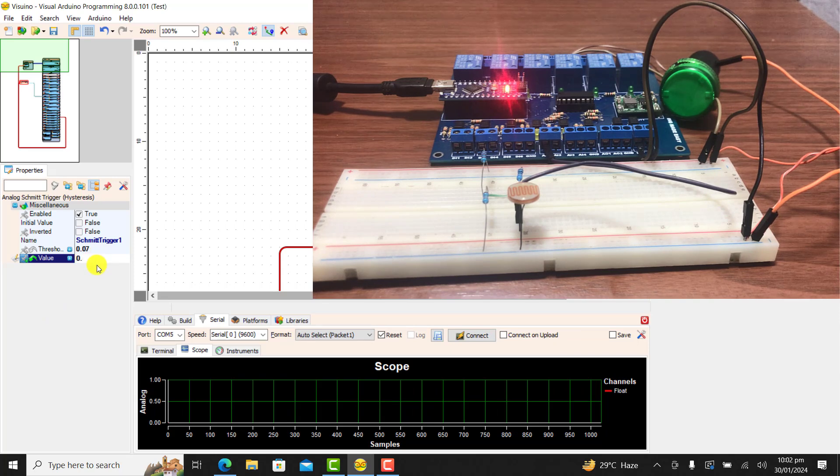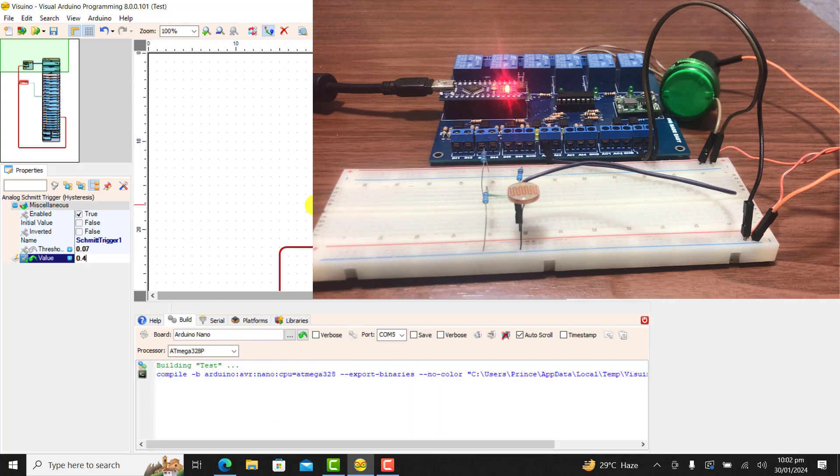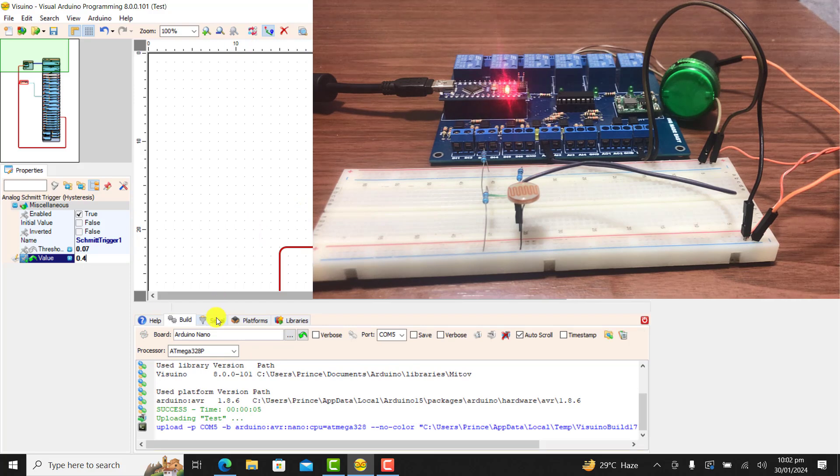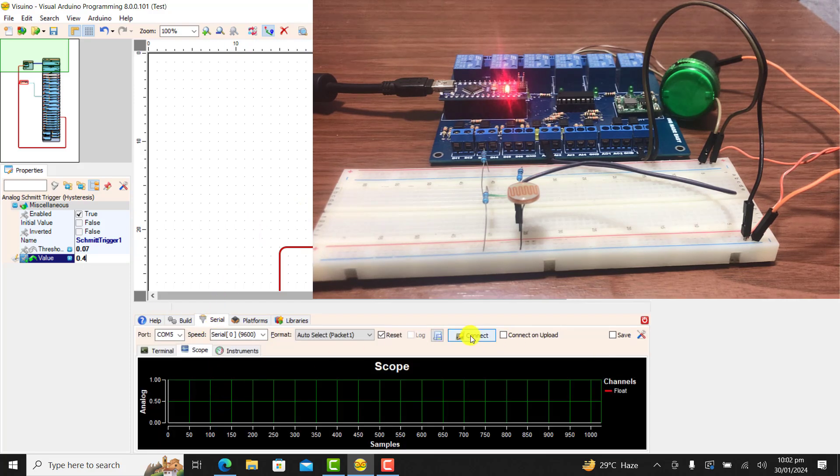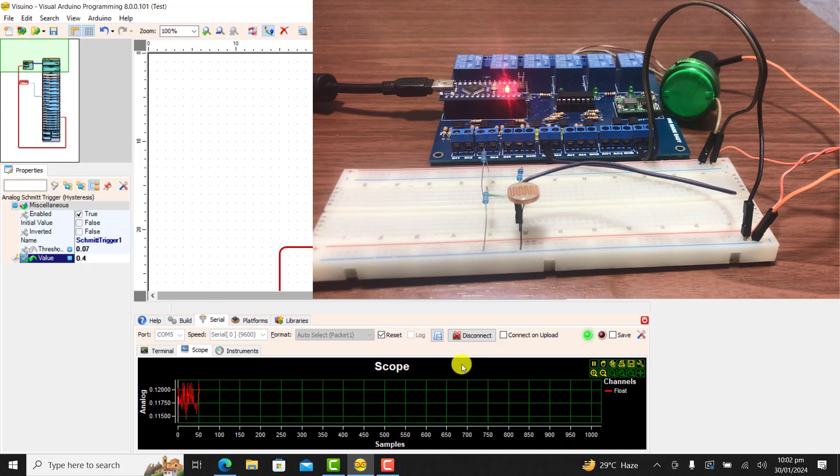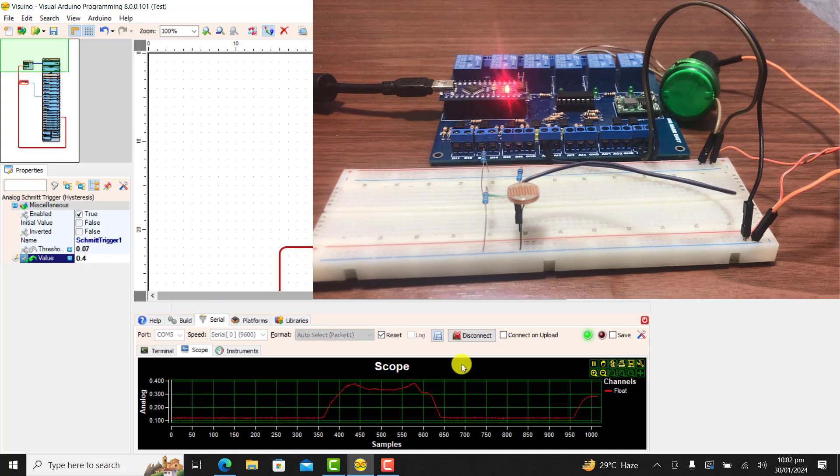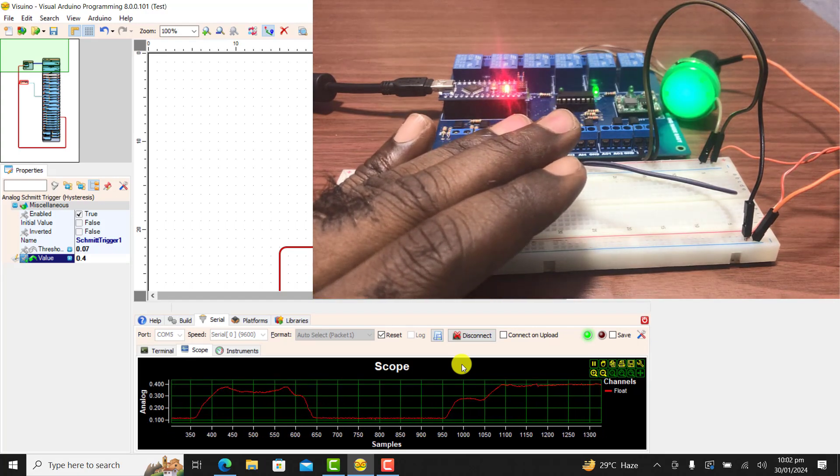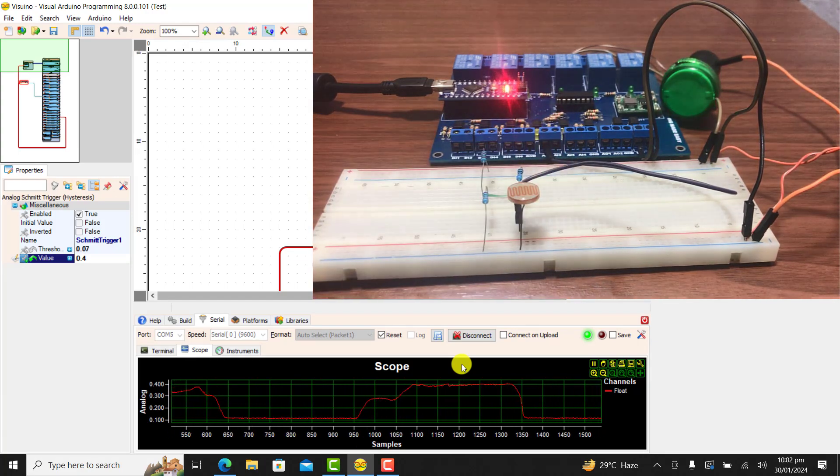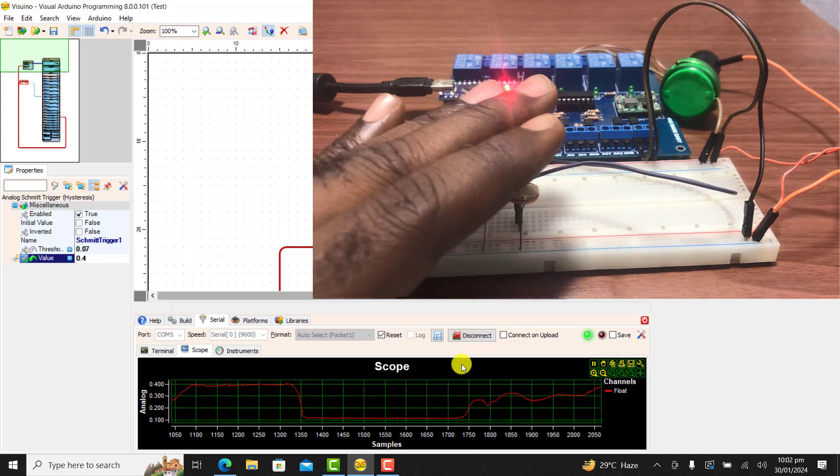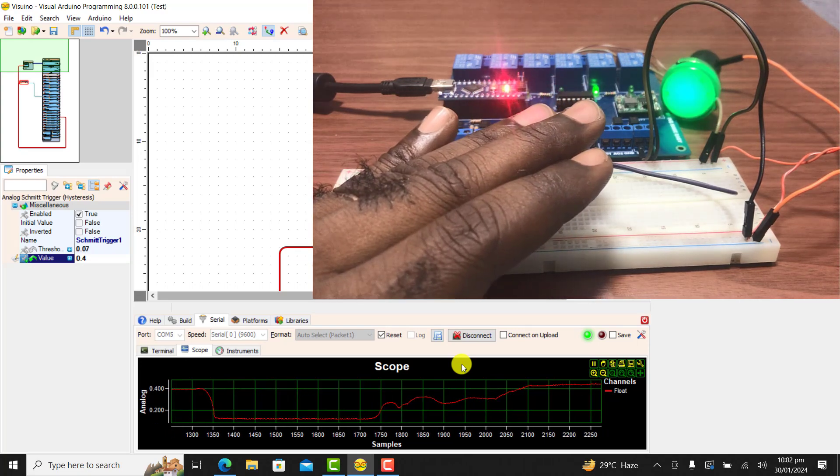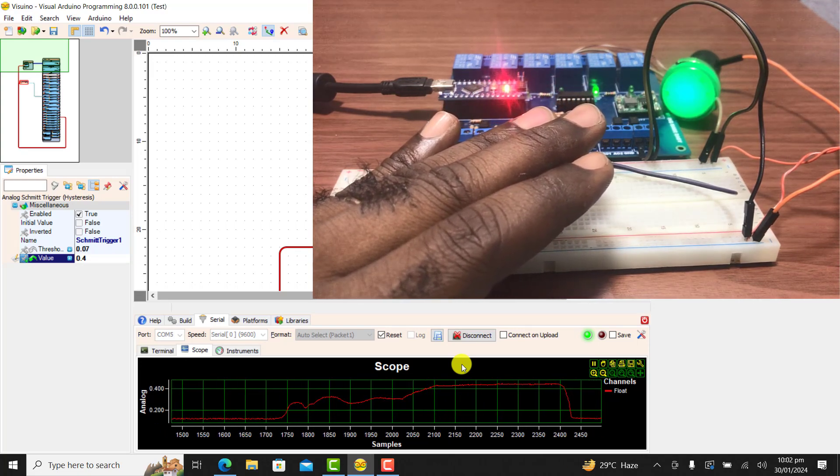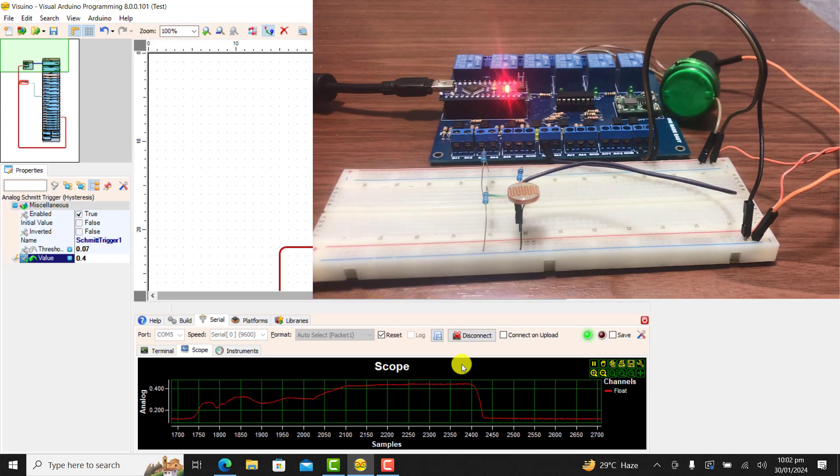I change the value now to 0.4 and then download once again to see how it will behave. And remember the more closer you get to your max value, the less sensitive the system becomes. Okay, I download. Uploading is done. I block it once again and you can see I need to block it very well before the relay energizes. I block it once again. Working perfectly.